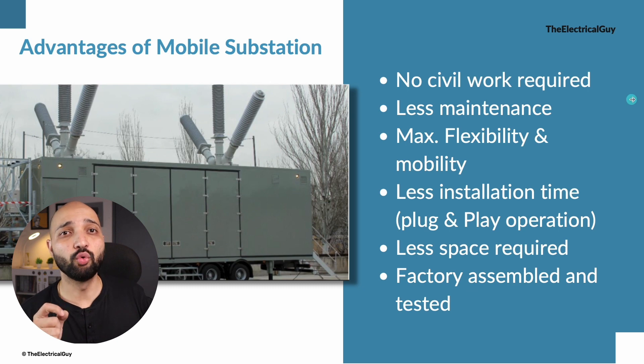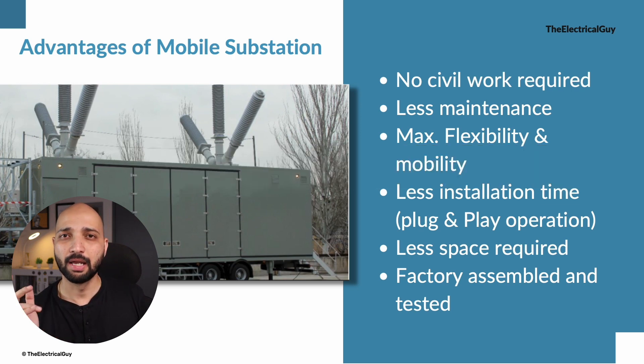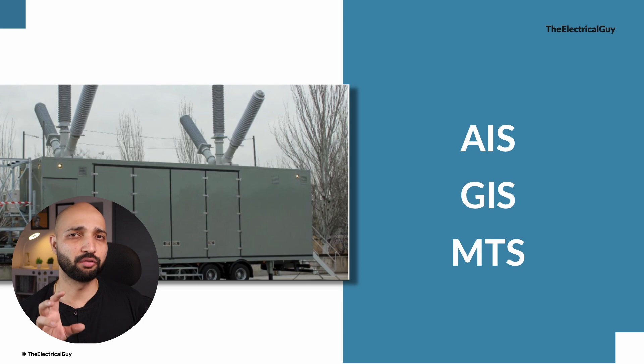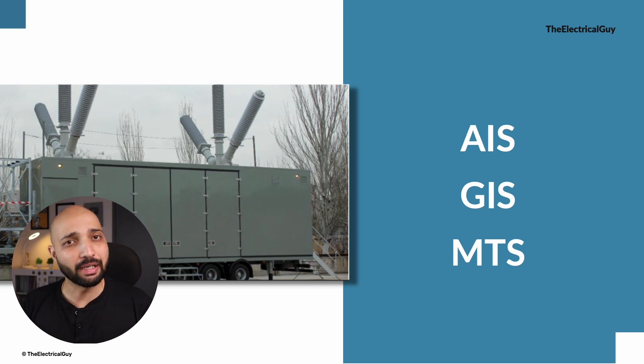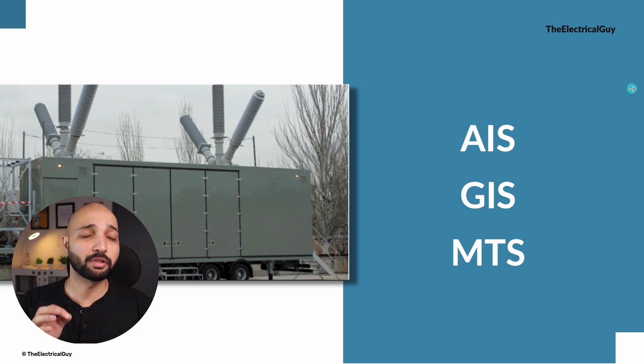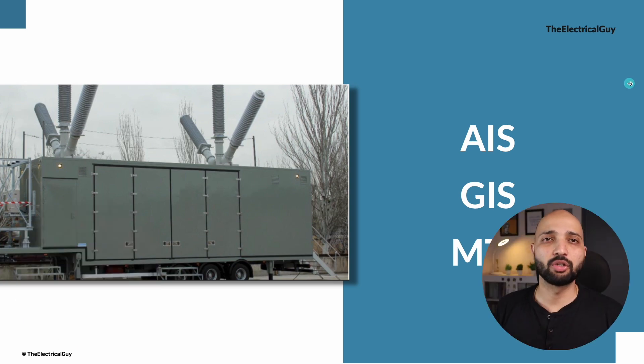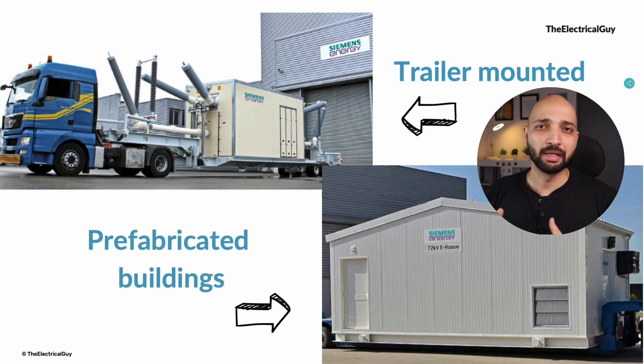These mobile substations are meant for quick operation — it's a plug-and-play type substation. As for switchgear technology, mobile substations do not use any special type. The same technologies used in conventional substations apply: air insulated switchgear (AIS), gas insulated switchgear (GIS), or hybrid mixed technology switchgear. These are the technologies used in mobile substations as well. The mobile substation can be trailer-mounted or mounted in a prefabricated building.